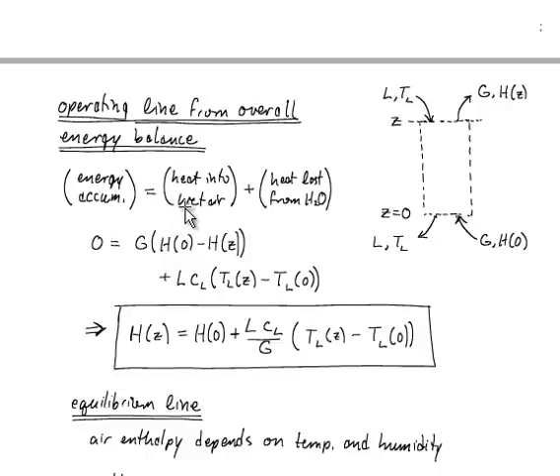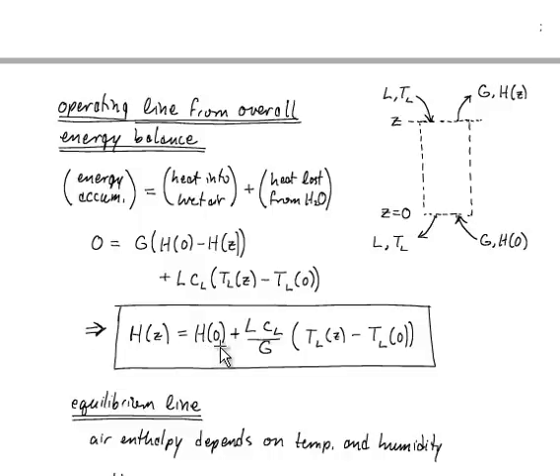At steady state, zero equals the heat flow into the wet air — the dry air flow rate G multiplied by the difference in enthalpy between the inlet at the bottom and the outlet at the top — compensated exactly by the heat lost from the water stream. This gives us that the enthalpy at the top equals the enthalpy at the bottom plus L times Cp of liquid divided by G, multiplied by the temperature difference of the liquid stream. This is our operating line.